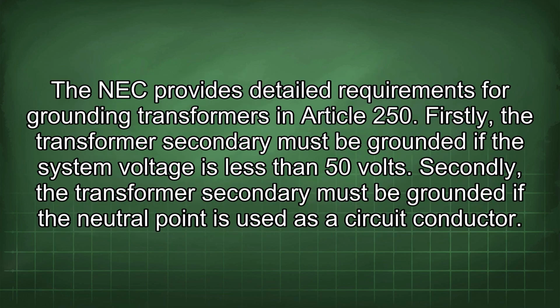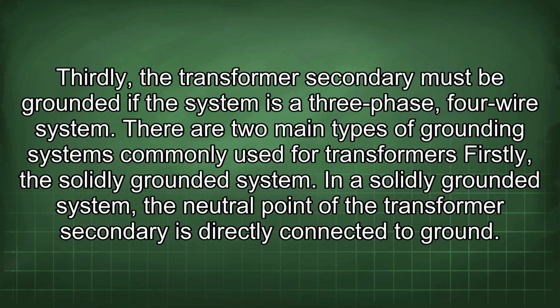The NEC provides detailed requirements for grounding transformers in Article 250. Firstly, the transformer secondary must be grounded if the system voltage is less than 50 volts. Secondly, the transformer secondary must be grounded if the neutral point is used as a circuit conductor. Thirdly, the transformer secondary must be grounded if the system is a three-phase, four-wire system. There are two main types of grounding systems commonly used for transformers. Firstly, the solidly grounded system.